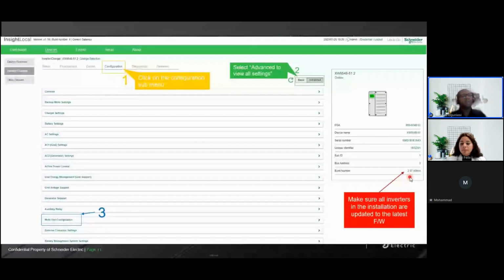So let's assume I have a bunch of inverters — say 6 inverters, or 3, or 2. As long as they're going to be connected together for the same load, I have to make sure they are on the same firmware. To make things easier, just make sure they are on the latest firmware to take care of old bugs that have been in the system. So make sure that is possible.